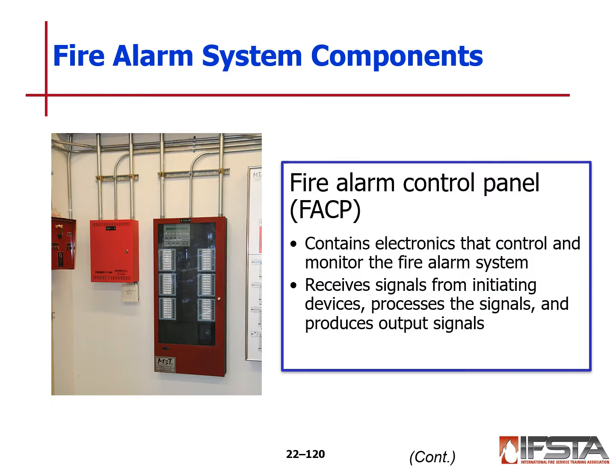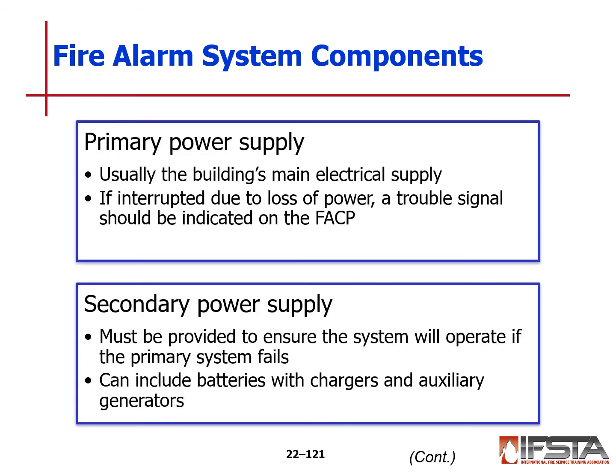Components of your systems: your fire alarm panel, which contains electronics that control and monitor the fire alarm systems. Basically, these receive signals from initiating devices, process the signals, and then produce an output signal. It gives either a local alarm or both a local alarm and an alarm to alarm companies.